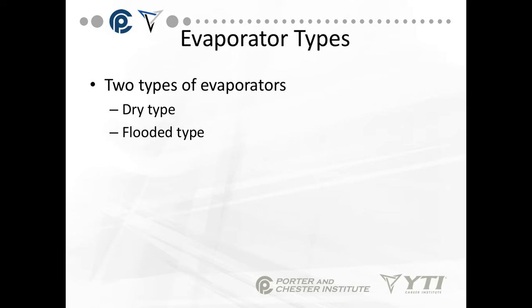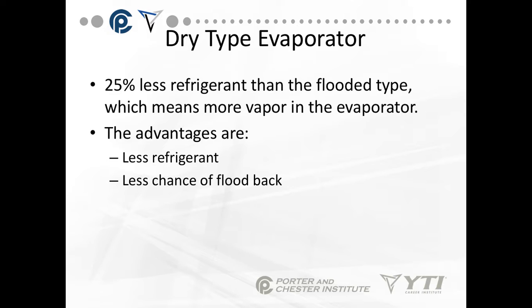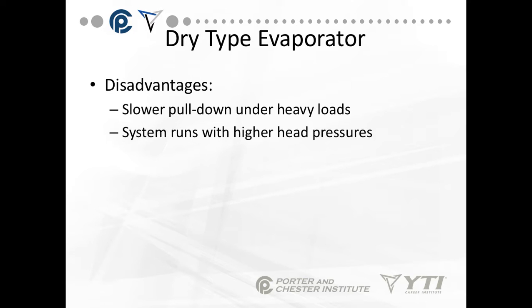We have two types of evaporators: dry type and flooded type. The dry type evaporator has 25% less refrigerant than the flooded type, meaning there's more vapor in that evaporator. The advantages of the dry type are less refrigerant and less chance of flood back to the compressor, since compressors can't handle liquid refrigerant. The disadvantages are a slower pull-down under heavy loads and slightly higher operating pressures.